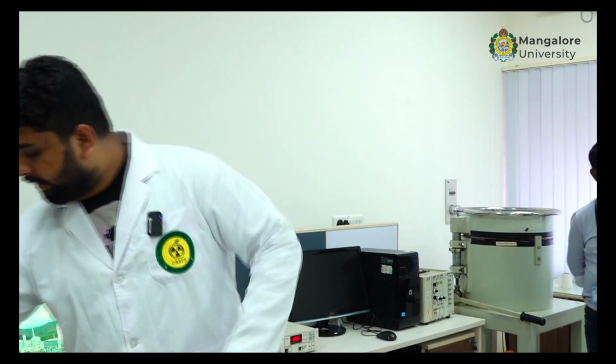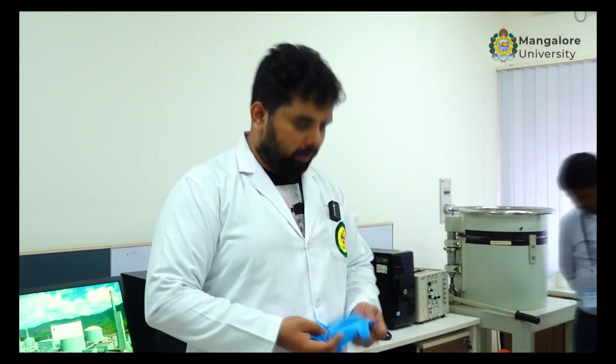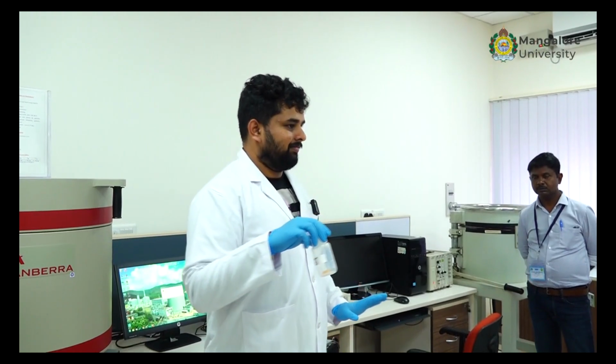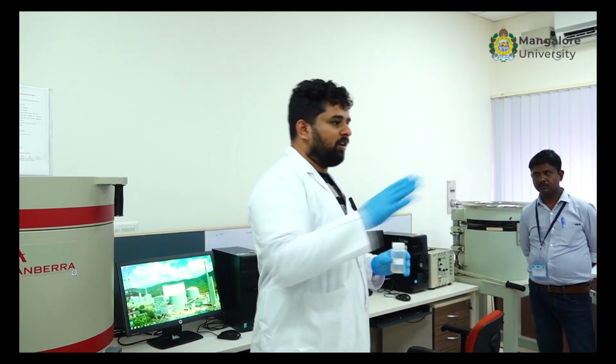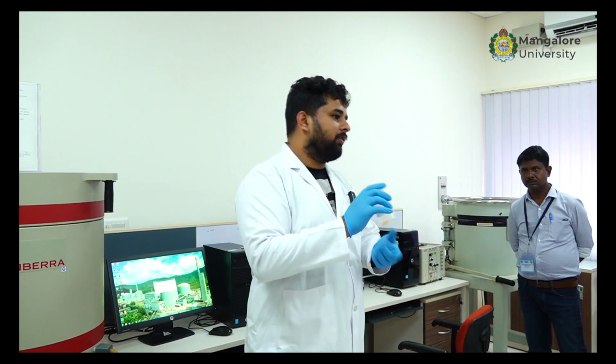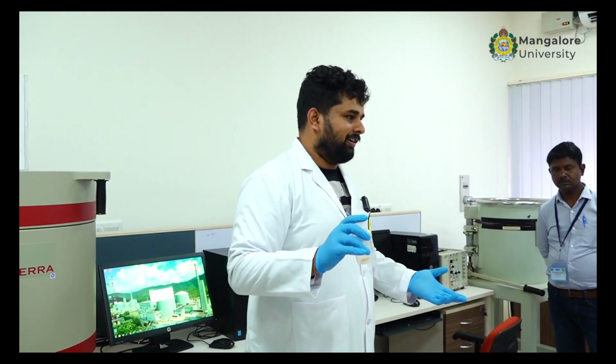How we maintain it here is by having a separate locker room for all these sources, and we make an entry on who has taken it, and he has to return it as soon as possible. If it is missing, he is the one who is responsible for the source. So this is about source handling. A point source can be lost anywhere, but it is easier to find. That is the only concern. And point sources we don't use for calibration, except for energy calibration. Efficiency calibration using point sources is not done, correct?